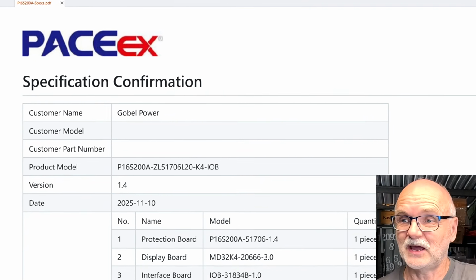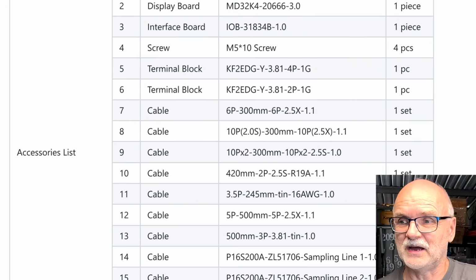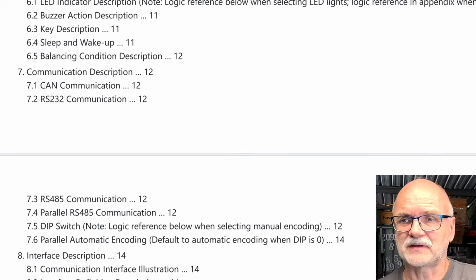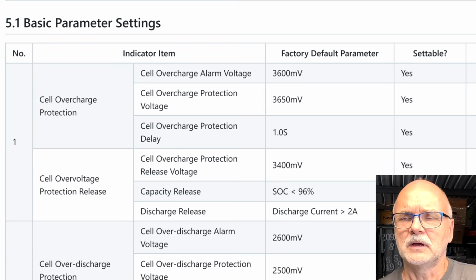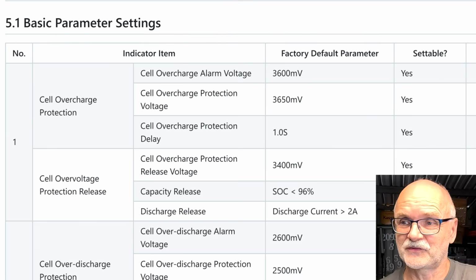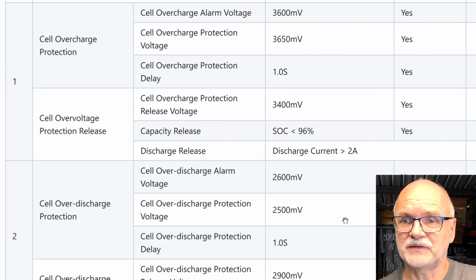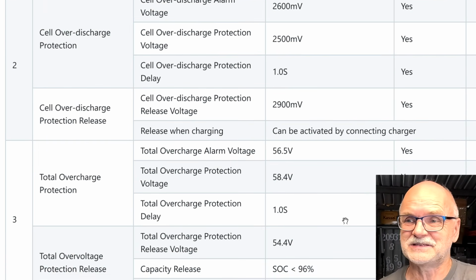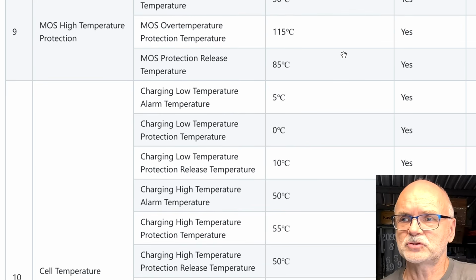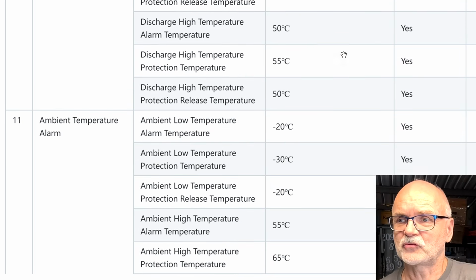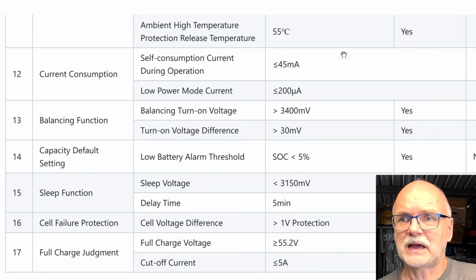So let's have a look at the specifications of this BMS, what we can find. And I want to highlight some of the features to you. Parameter configuration. So basically all the parameters can be set by yourself. These are the default parameters you can see here. I don't want to go through all these parameter settings here and discuss them. Okay, these are the temperature alarms. Not too interesting. Current consumption smaller than 45 milliamps. In low power mode, it even takes less than 200 microamps. Wow. Balancing function 3.4 volts. It turns on, but you can change this setting.